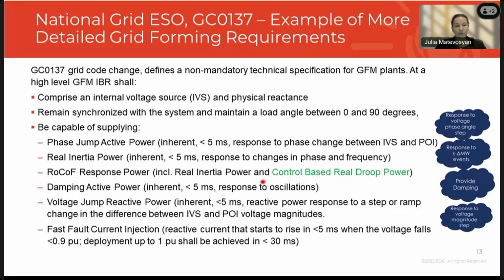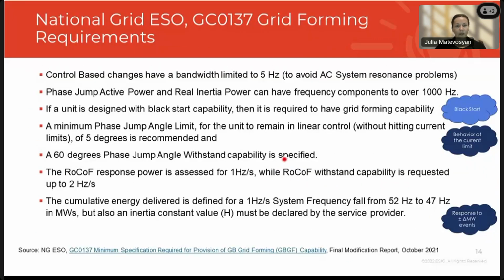Damp active power, voltage magnitude jump reactive power provision, and fast fault current injection, which is in a time frame less than 5 milliseconds. So again, you can see these common themes that I had on the first slide before I went into each of the specific requirements. They say if the unit is designated to have black start capability, then it is required to have grid forming capability. So again, underlying that not all units will be required to be black start capable and be over-dimensioned. Therefore, there is a minimum phase jump angle limit at which a grid forming inverter-based resource is not supposed to hit its current limits. And the recommended limit currently is 5 degrees. And then there is 60 degrees phase jump withstand capability that is specified. So that's basically a ride-through of phase jump, where a grid forming inverter-based resource is not supposed to disconnect.